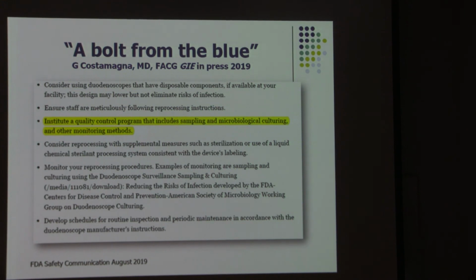In reality, and this is based on expert opinion, not data, manual cleaning followed by automated reprocessing, followed by manual cleaning and again automated reprocessing is probably what disrupts the biofilm most, but it is labor intensive. It's going to add additional time to your duodenoscope processing, and each institution should evaluate that. But it's entirely possible that what we're all doing, just pushing the button on the washer and doing it one more time, is probably not going to do it, although the data is quite flawed and the studies were underpowered.